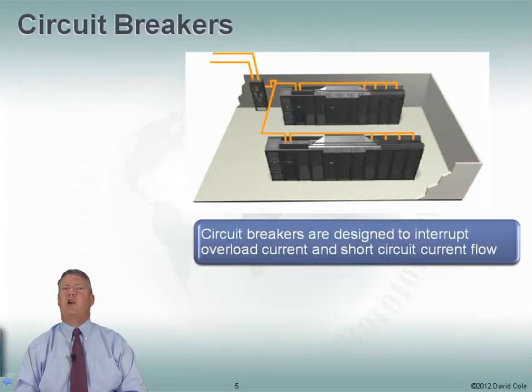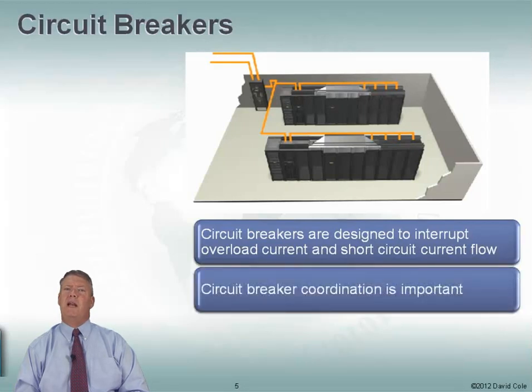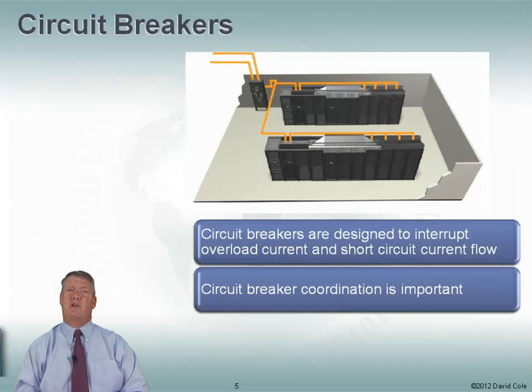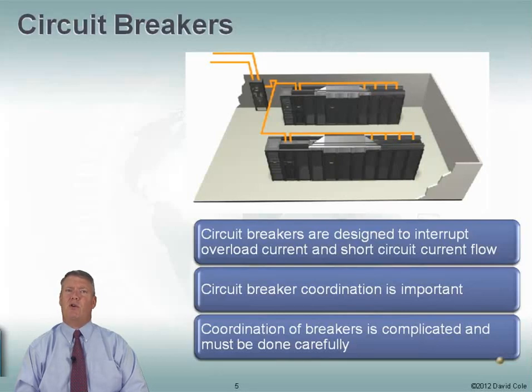It's really important that we coordinate circuit breakers inside the data center. These circuit breakers are designed to interrupt overloads and short circuits. Coordinating them is important because we want the circuit breaker to blow — or pop, as it's sometimes called — as close to the equipment as possible. We want the least amount of equipment to come down when a circuit breaker pops. So it's complicated to do this and must be done carefully. I'm going to walk through an example of how this circuit breaker coordination happens.